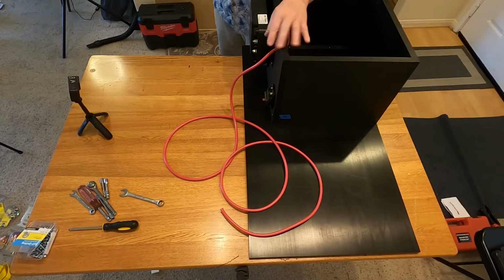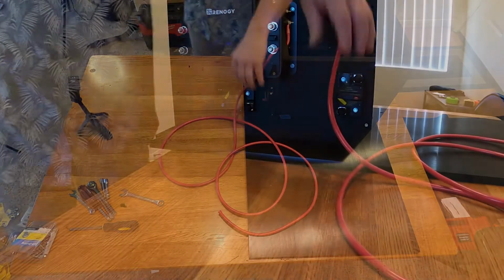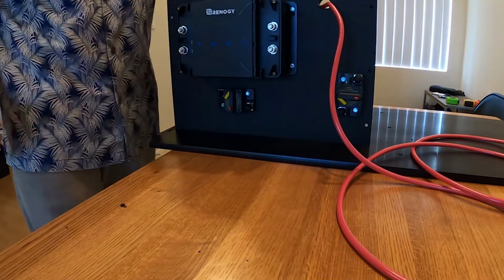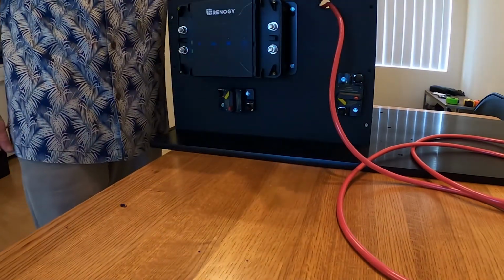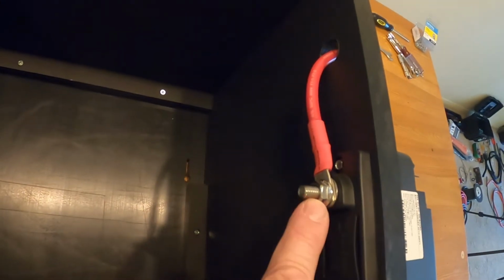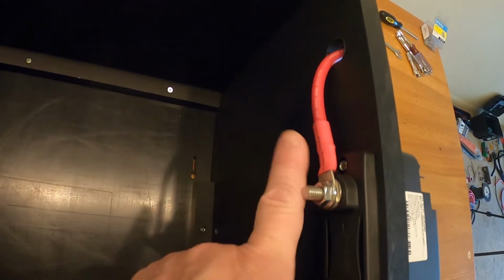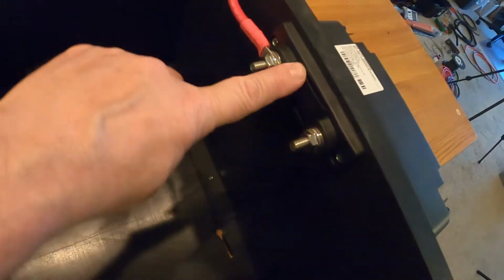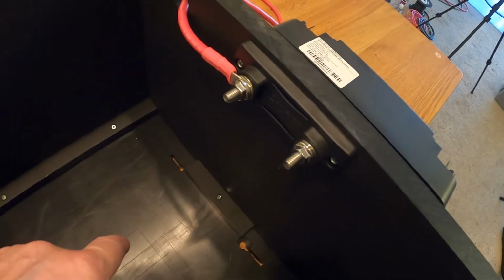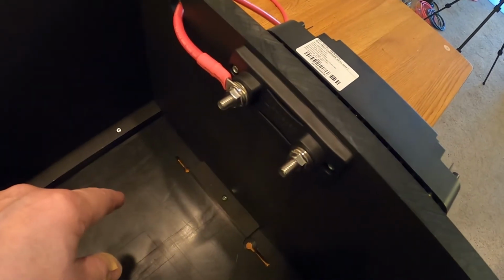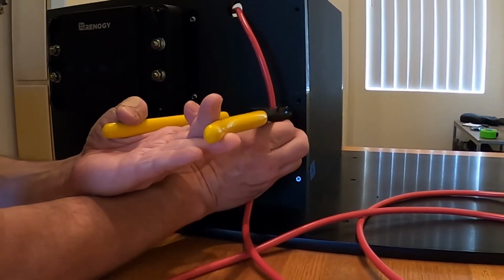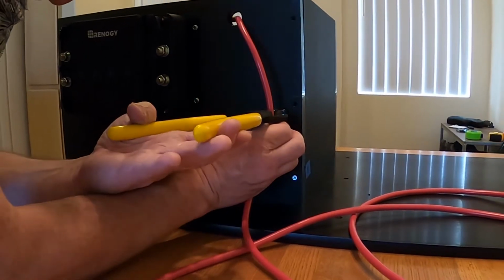Essentially what I'm trying to do here is get the lengths measured out so I can cut my cables and terminate the lugs onto the cable. I'm starting with this 6-gauge wire, and I'll run a 2-gauge wire from this point out to the battery. A 200 amp fuse, or maybe a 225 amp fuse, and then the inverter is going to be mounted over that direction. So I'm going to pull it kind of tight and then cut directly over the terminal.